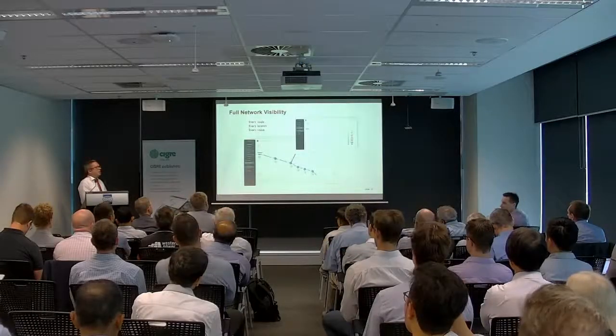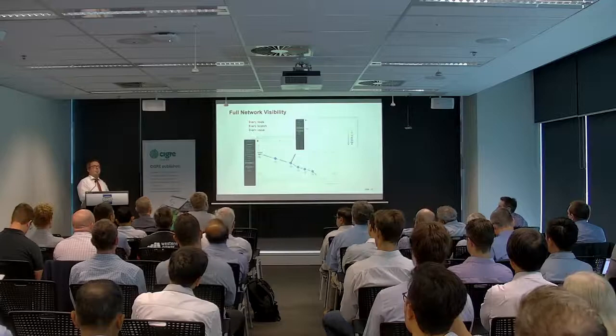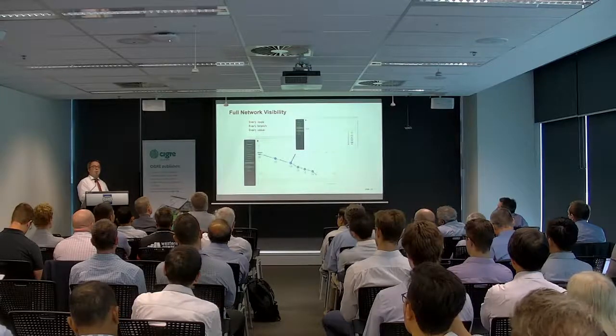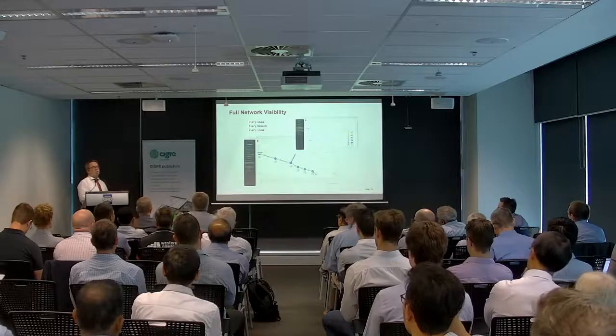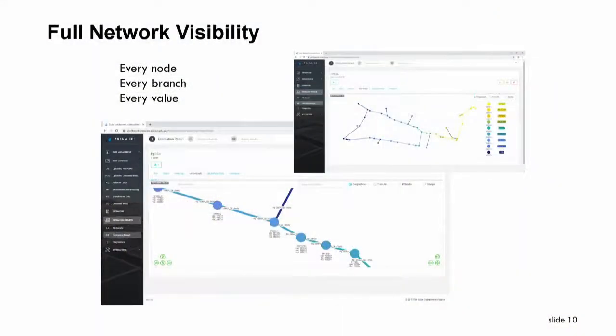Under the bonnet of this particular project is a state estimation implemented on a 4-wire network model, aiming at low voltage networks and capturing all the details that low voltage networks normally require you to model. The idea was that low voltage networks are probably the most complex to model, and once you've done that, the rest becomes relatively easy.